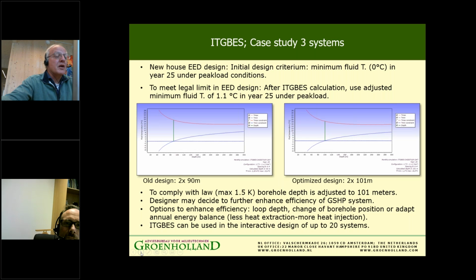Obviously, you are as a designer completely free to say, look, I am still less efficient than I would have been if I had been able to achieve the 0 degrees criterion in year 25. So I may want to improve this any further. Or your client may wish, for instance, an even further improvement. And then you can use this tool to change your EED design again for your house and raise the temperature to a level that you find acceptable. The options that you have to enhance your efficiency, you can obviously, as we've done here, increase the loop depth.